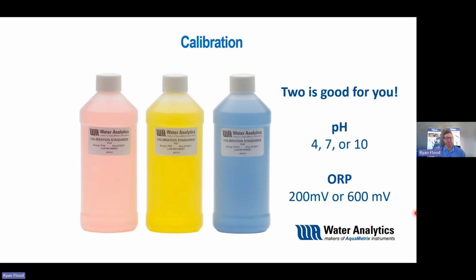The nice part about the pH 7 buffer solution here as well is that's also what we use in our reference solution. So there's other sensors on the market that may just use like a KCl reference solution, and you'll need to keep that on hand. For us, one of our advantages of the differential sensor that we make and manufacture is the reference solution is just simply pH 7. So that's what we always say when you're doing 2-point calibration, pick 7 as one of your solutions, because you're already going to need that for your reference solution as well. And it really just helps cut down the number of materials you're going to need to perform calibration and maintenance.